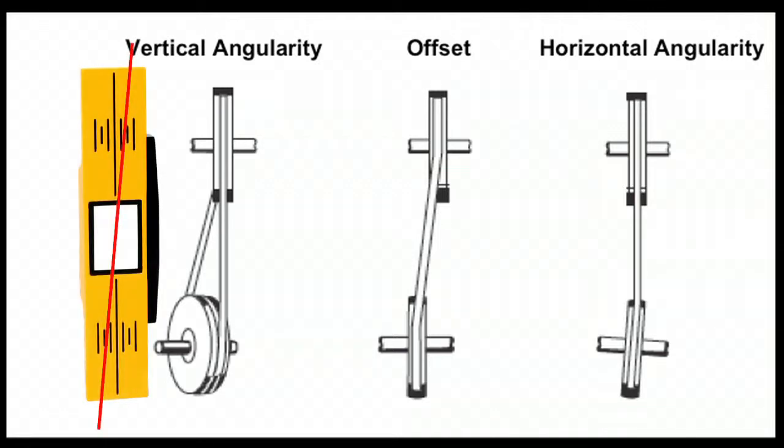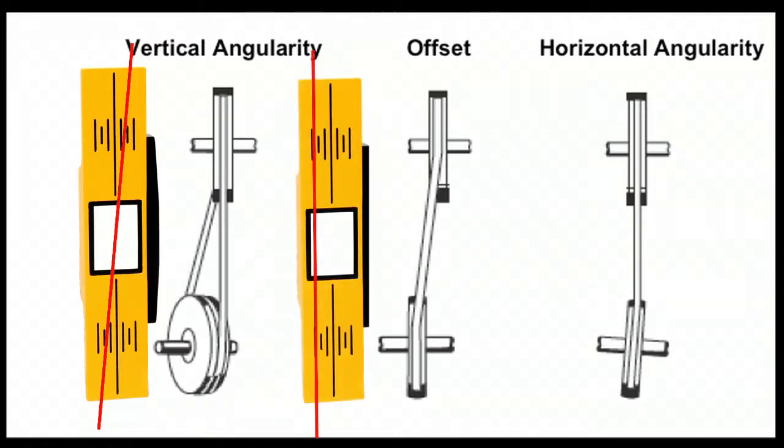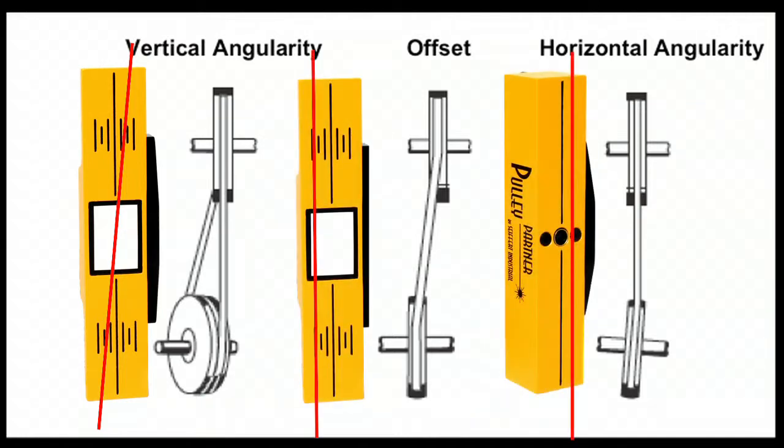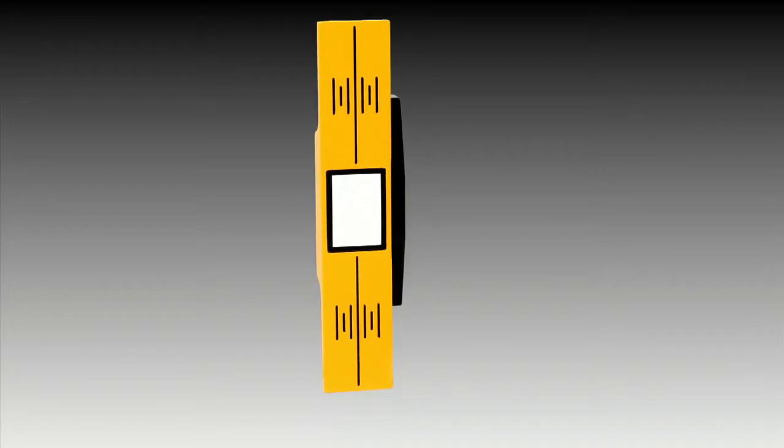The position of the transmitted laser line on the reflector indicates vertical angularity and the offset. Horizontal angularity is indicated by the position of the reflected laser line onto the transmitter. For different pulley edge thicknesses, use the offset marks on the face of the reflector to establish the amount of offset. These marks are in eighth-inch increments.